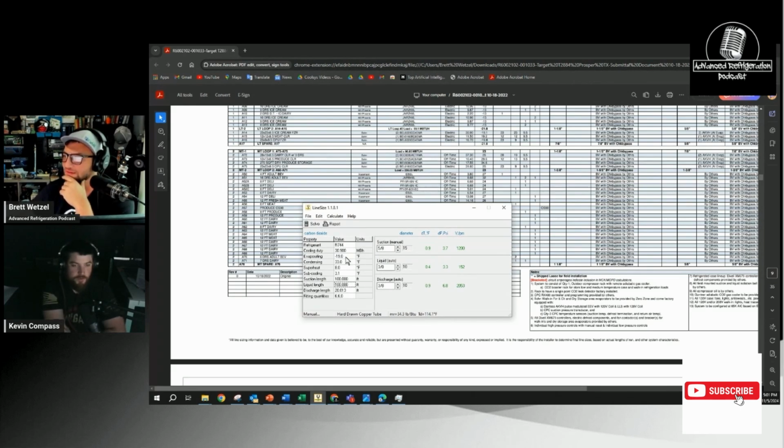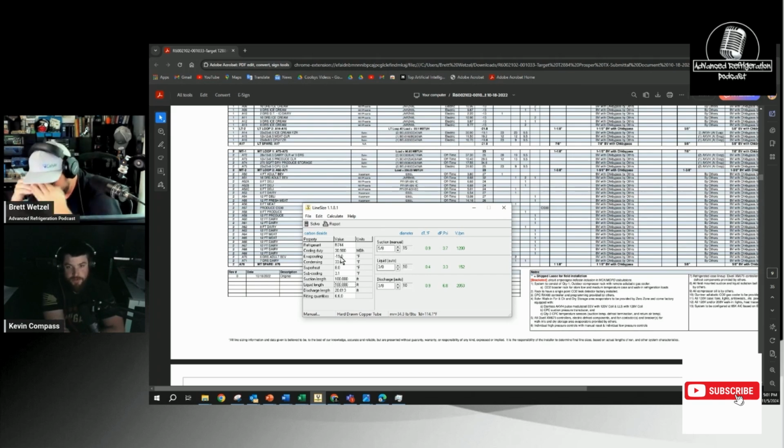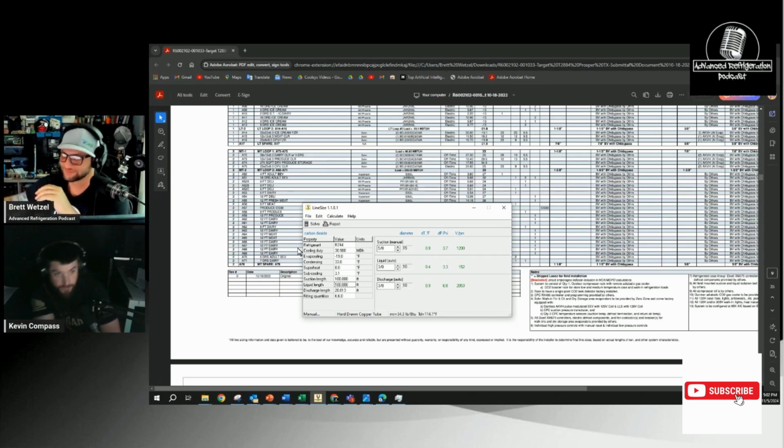So this is why they're always wrong, and this is why all the pulse valves come out wrong. And then you get the liquid hammer extreme because you've got Hussmann saying they need a plus 28 coil, Kysor Warren saying they need a plus 26, Hill Phoenix saying they need a plus 18 for some random case. Then the whole rack is sized for plus 18, and the whole rack is running plus 18, and nothing else is getting plus 18. The pressure drops almost double, and every valve is like two sizes too big. In 6 seconds, it just gives you nothing but full flood. Seen it 100 times.